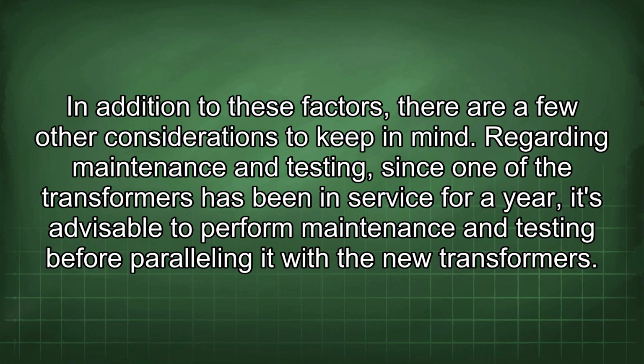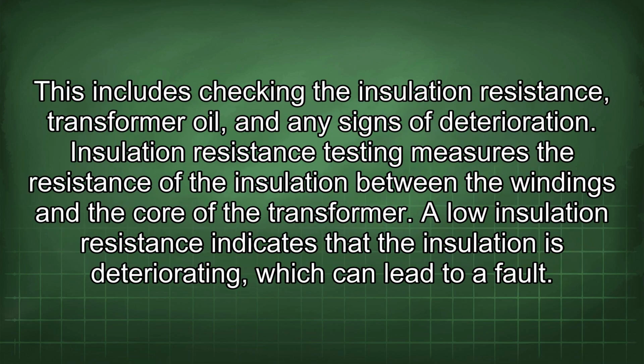Regarding maintenance and testing, since one of the transformers has been in service for a year, it's advisable to perform maintenance and testing before paralleling it with the new transformers. This includes checking the insulation resistance, transformer oil, and any signs of deterioration. Insulation resistance testing measures the resistance of the insulation between the windings and the core of the transformer. A low insulation resistance indicates that the insulation is deteriorating, which can lead to a fault.